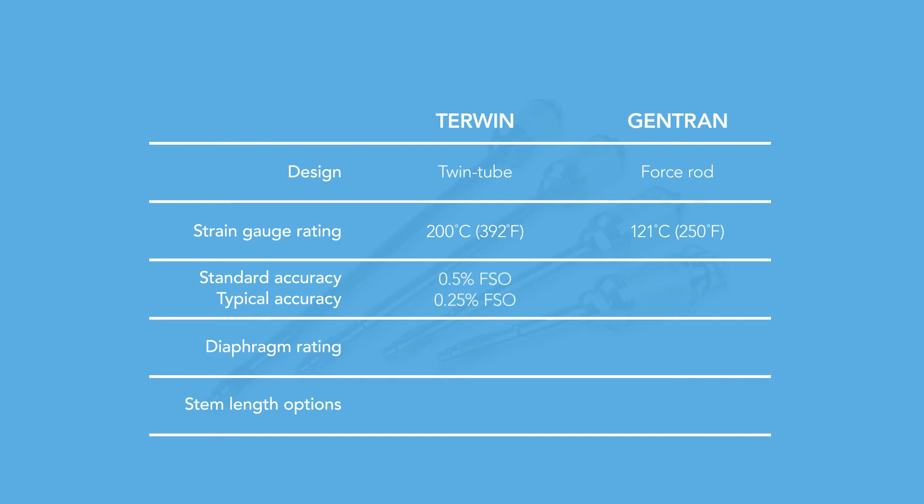Terwin's standard accuracy is within 0.5 percent of the full range, and typically within a quarter point full range. The diaphragm is rated at 450 degrees Celsius, and they make different rigid stem lengths.